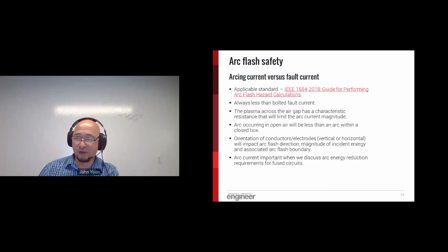We're running short of time, so let's make this quick. Again, the arcing current will be significantly less than the bolted fault current, somewhere around a third to half of the bolted fault current. You're conducting that current through an ionized plasma, bridging an air gap between energized conductors and a grounded component. When it happens in an enclosure like a panel or switchboard, the enclosure serves to magnify and direct the released energy, which makes it more dangerous for an electrician working in front of a piece of equipment.